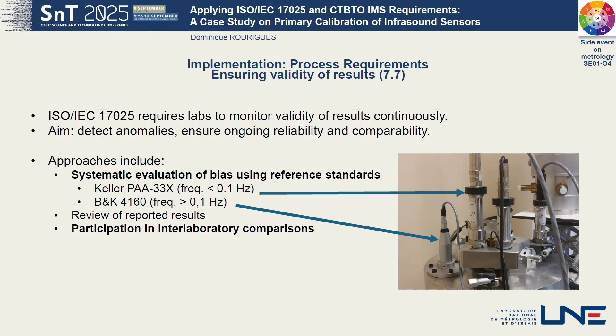it's a planned activity. So we have a plan for that, and usually we have to make 1 interlaboratory comparison per cycle of accreditation. In France, 1 cycle is 5 years. But as the method is quite new, we also implemented another thing, which is a systematic evaluation of bias by using other reference standards. So for each calibration, we always have 2 reference sensors to monitor the results: 1 barometer to monitor the results at low frequencies, and 1 microphone to monitor the results at high frequencies.